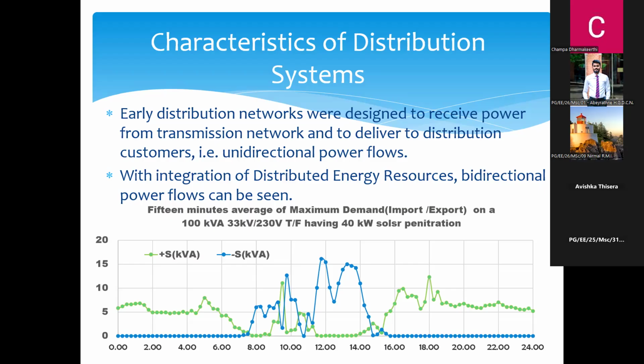So you can see early in the morning, 1 a.m., 2 a.m., 4 a.m., it's consumed power. That means importing power from the transmission side. And once it reaches 7 o'clock in the morning, close to 8, it starts exporting power. You can see in between it is even importing power. Maybe this is due to cloud effect, or maybe at that point of time the load has increased beyond the solar generation. So in some 15 minute intervals, it has changed from import to export.